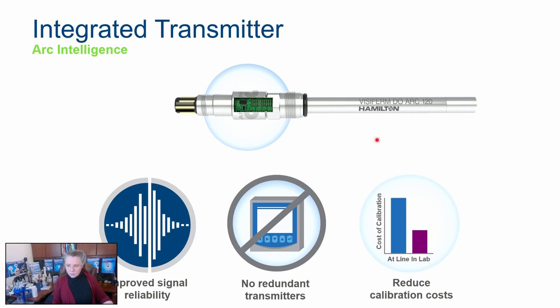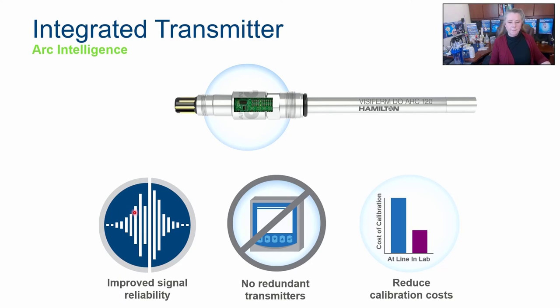When I talk about intelligent sensors, these are the sensors of the future, and they're where everything is going. They have no need for transmitters. Everything from a transmitter is built in and integrated into the sensor head, along with the ability to store data and calibration. They give you a much more robust signal because they're digital versus analog. I could bat that cable all day long and it won't even blink at me. Because you can calibrate and know at a glance if your sensor's okay, it reduces a lot of maintenance time.